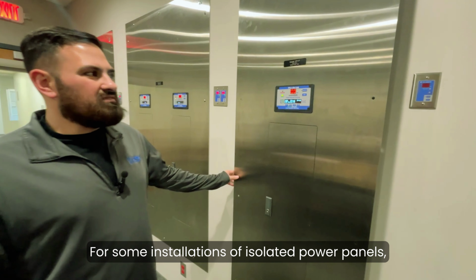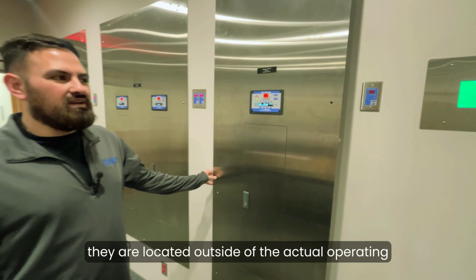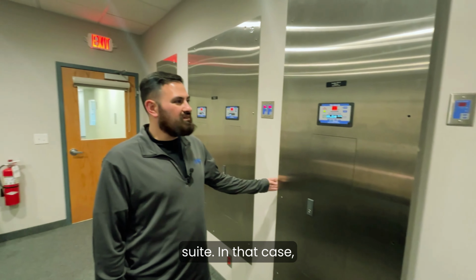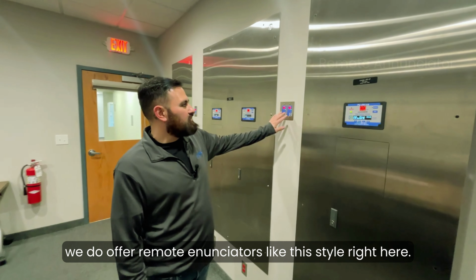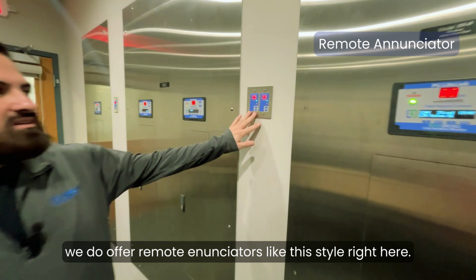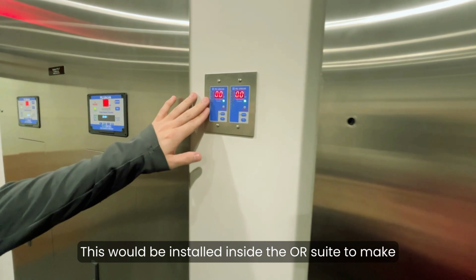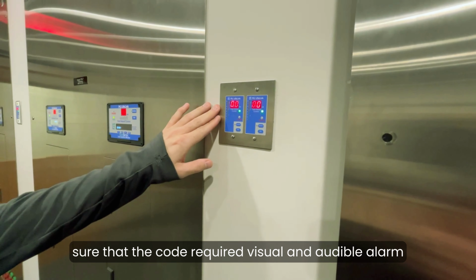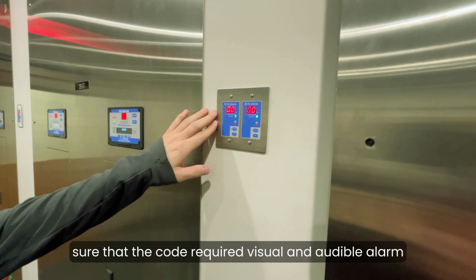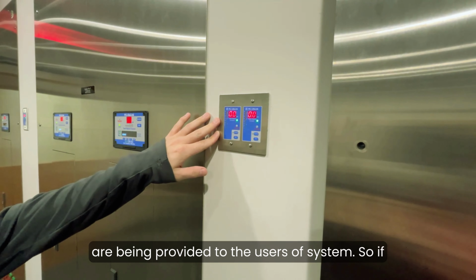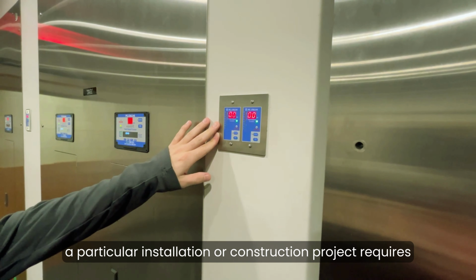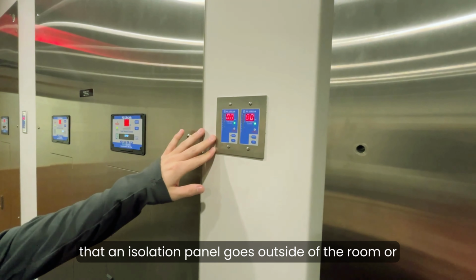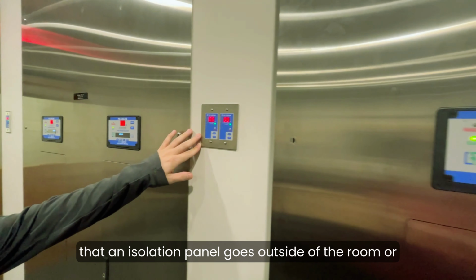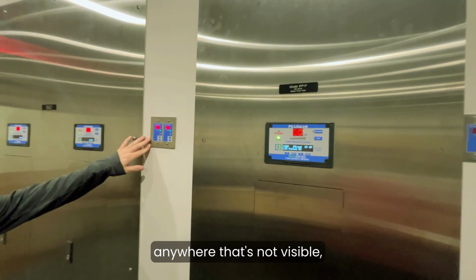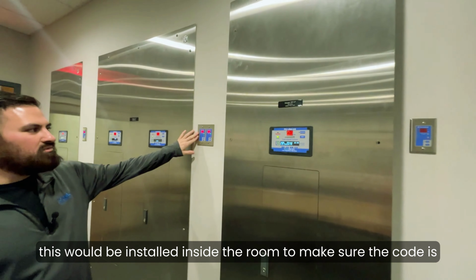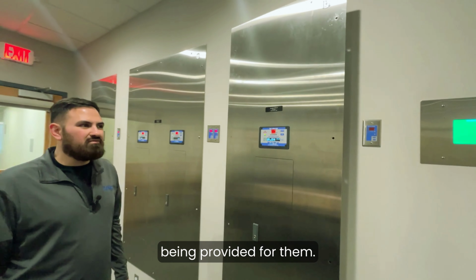For some installations of isolated power panels, they are located outside of the actual operating suite. In that case, we offer remote annunciators like this style right here. This would be installed inside the OR suite to make sure the code required visual and audible alarms are being provided to the users of the system. So if a particular installation or construction project requires that an isolation panel go outside of the room or anywhere not visible, this would be installed inside the room to make sure the code is being met.